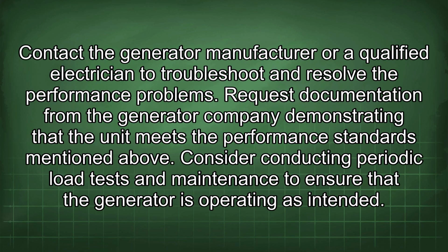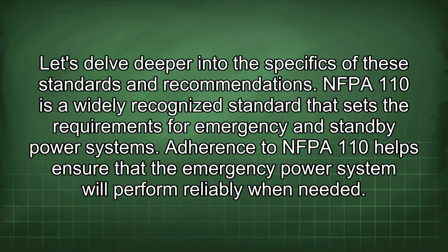Contact the generator manufacturer or a qualified electrician to troubleshoot and resolve the performance problems. Request documentation from the generator company demonstrating that the unit meets the performance standards mentioned above. Consider conducting periodic load tests and maintenance to ensure that the generator is operating as intended. Let's delve deeper into the specifics of these standards and recommendations.